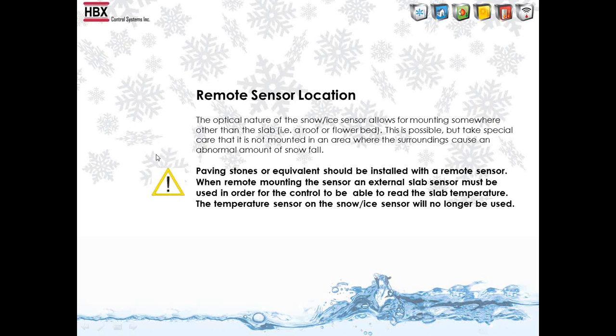So the SNO-0110 sensor would let us know when it snows, and the remote slab sensor would tell us basically what the temperature of that slab is, so that we can run the system properly. So one thing that we do definitely recommend, if you're using paving stones or something like paving stones, is that you use the control in the remote sensor application.